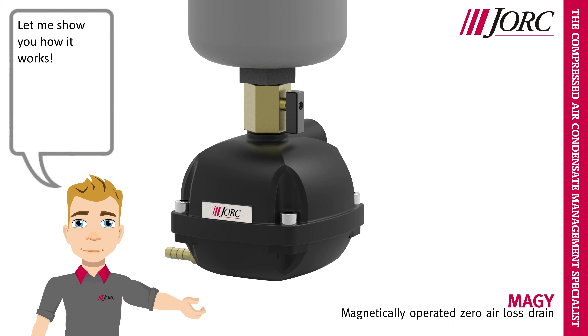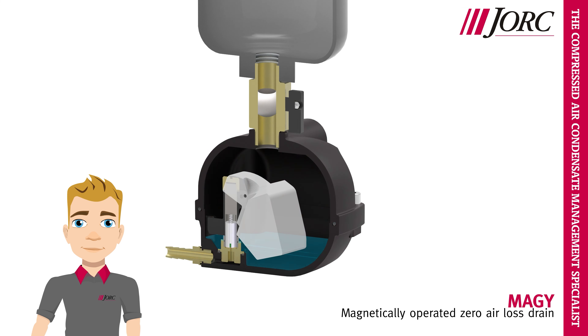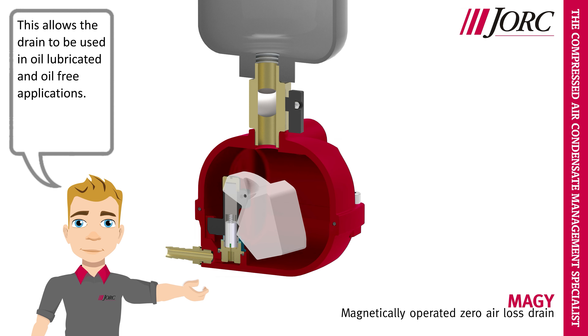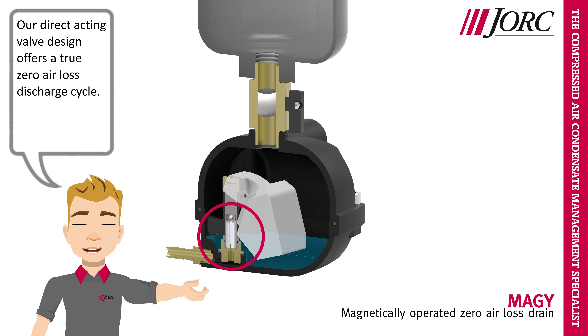Let me show you how it works. Notice the aluminium reservoir that is specially coated. This allows the drain to be used in oil-lubricated and oil-free applications. The MAGY uses specially selected magnets, that are situated in the operator, to open the solenoid valve. Our direct acting valve design offers a true zero air loss discharge cycle.